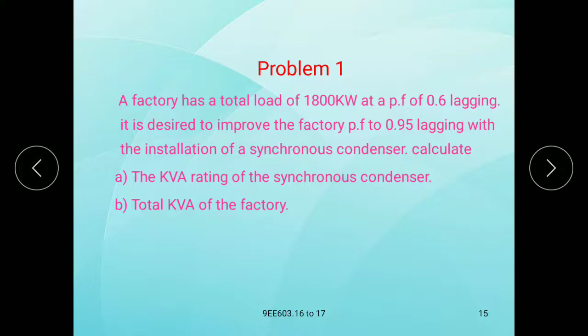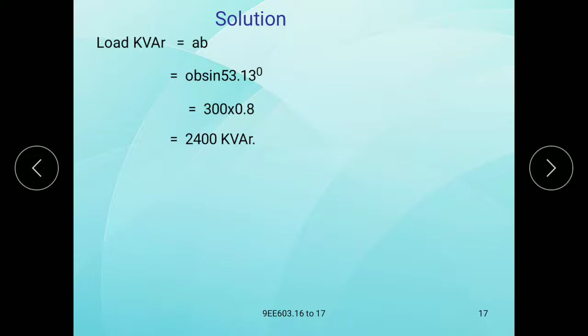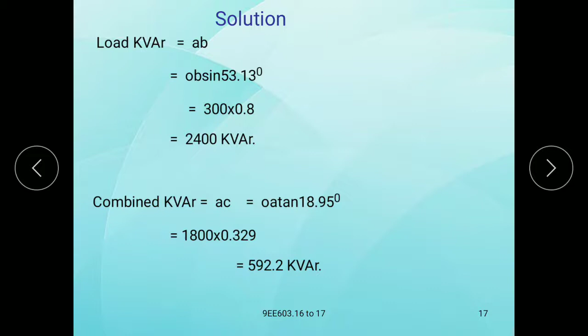From the vector diagram, load KVA is equal to 1800 by 0.6, which gives 3000 KVA. AOB is cos inverse 0.6, that is 53.13 degrees, and AOC is cos inverse 0.95, that is 18.19 degrees. Now load KVAR is equal to AB, that is OB sin 53.13, equal to 3000 into 0.8, that is 2400 KVAR. Combined KVAR is AC, that is 1800 into tan 18.19 degrees, that is 1800 into 0.329, which gives 592.2 KVAR.